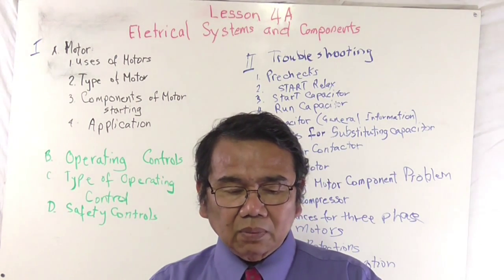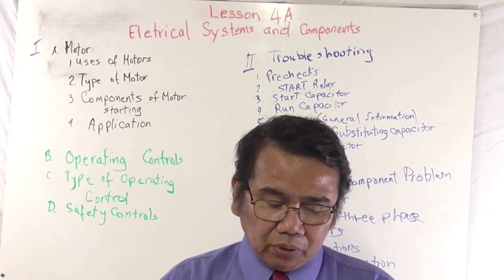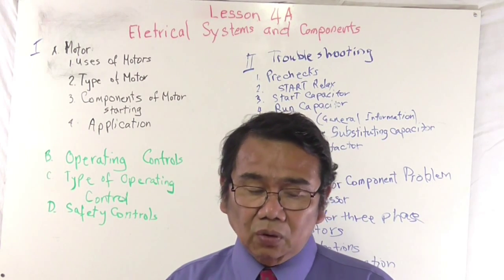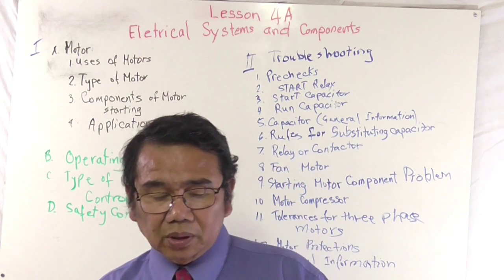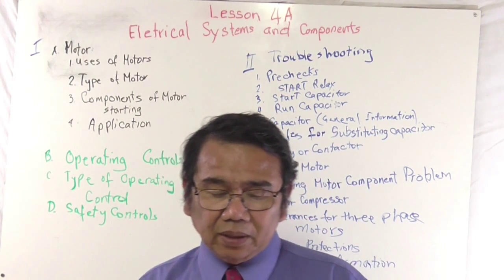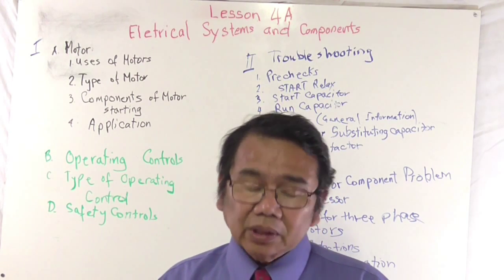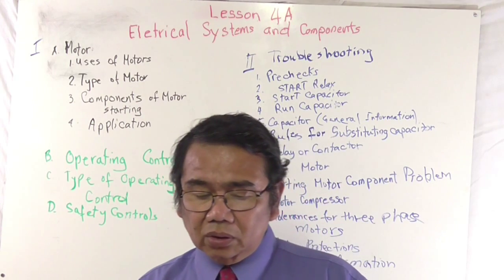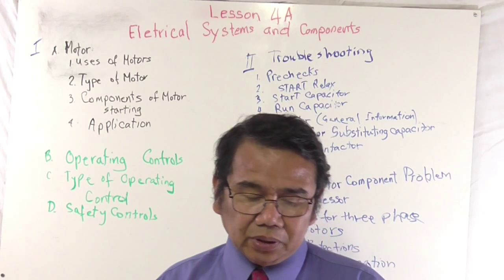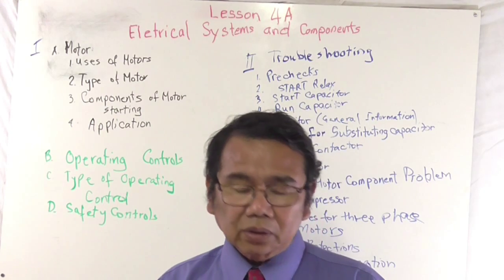Okay, we're talking now about 3-phase motors. Motor internal protector, used mainly on hermetic compressors, normally opens when temperature reaches 200 to 250 degrees. Generally two types: you got the bimetal disc and series heater coil, and you got the thermistor installed directly on or in the windings. Depending on ambient temperature, it may take 1 to 2 hours for the protector to close if it opens.